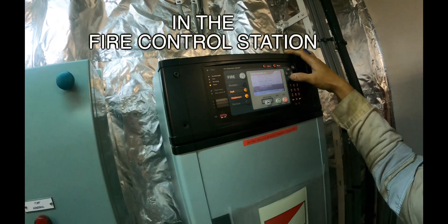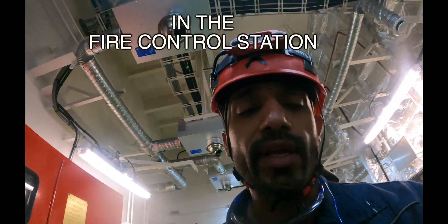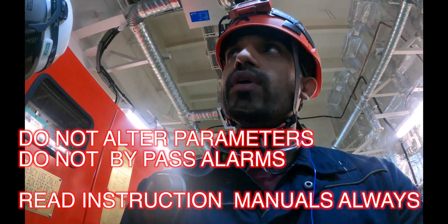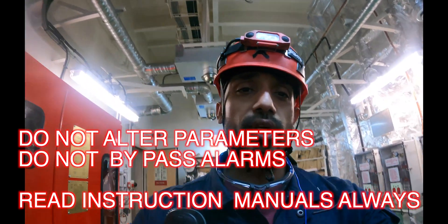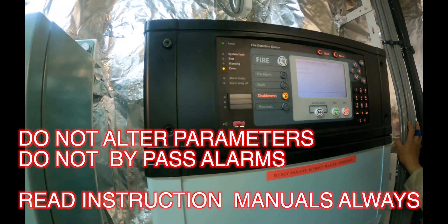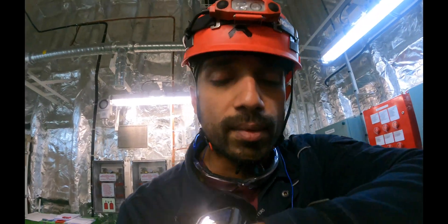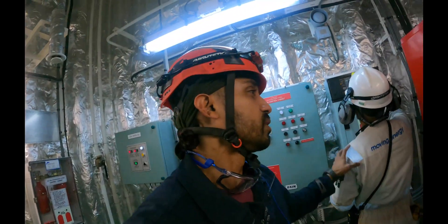Now we are at the fire detection panel. From here we will re-enable the fire loop that we had disabled. Read each and every instruction on the fire detector panel carefully — for example, this is a Salwico panel. Read the manual and only then touch these parameters. Please consult your chief engineer and don't do things on your own. The system now shows no more alarms. The previous loop fault was caused by salt on the circuit board, which caused a short circuit on that particular manual call point's circuit board.